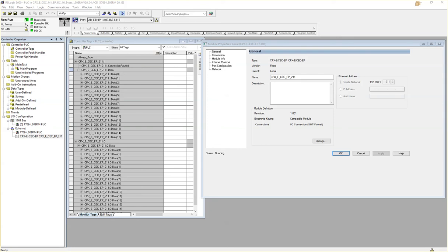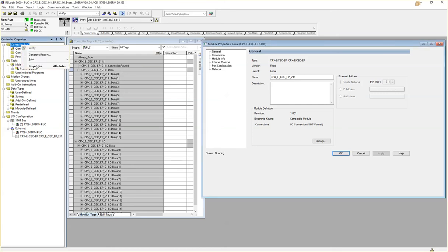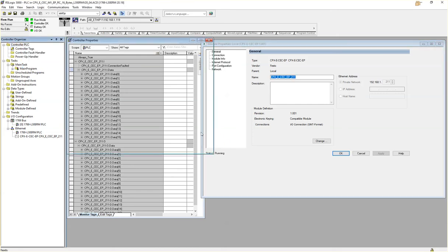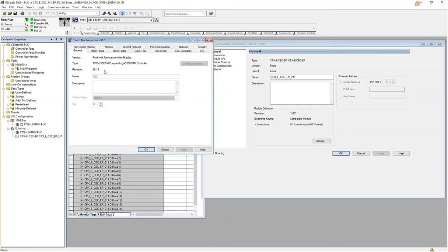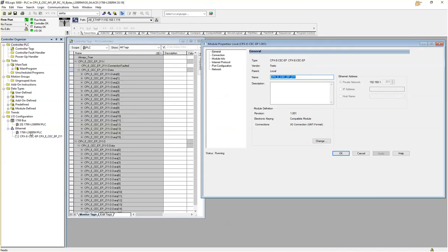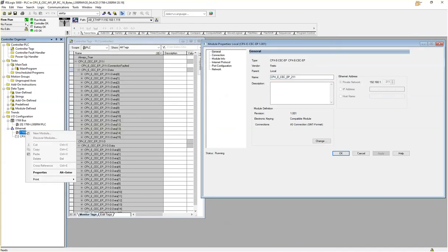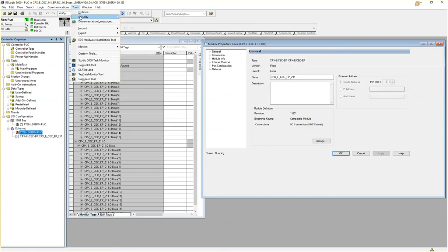Okay, so testing EDS file for CPX-E-CEC-EP. I have a version 20 ControlLogix or CompactLogix platform here, L30 ERM. I registered the EDS file simply by Tools menu, EDS installation, and I installed the EDS file with no issues. I was offline.